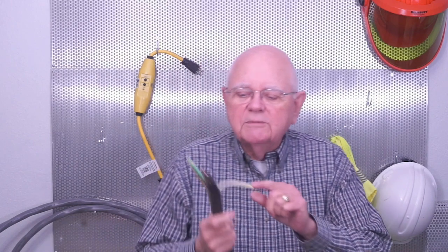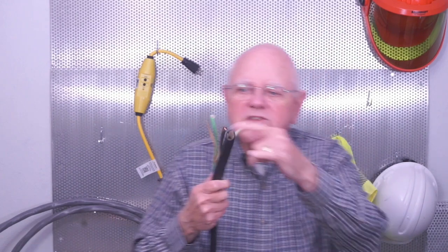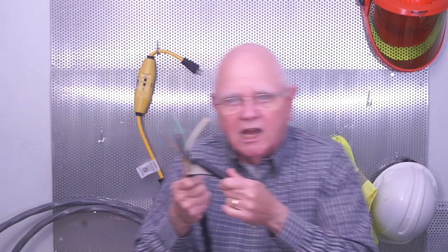Now, lots of times we just say, well, that's SO cable. No, it's not. It says it's SOOW. It depends on what you're using. SO is hard usage, so is SOW, and so is SOOW. The S is hard usage. The O, there's actually 2 O's in the SOOW, right? One of the O's tells me that the insulation on the conductors is oil resistant. The second O tells me that the jacket on the outside is also oil resistant. And then the W tells me that it's suitable for a wet location. So obviously that's important to know, especially in the construction world, isn't it?